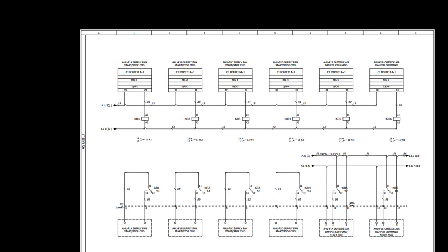Here are the terminal numbers of our panel: 9, 10 and 11. On terminal number 10 we have the on off command. This on off command is also 24 volt, but it is through the relay contact. When the relay opens, our damper will start opening, and when this relay is closed, our damper will start closing. But you can set this on the damper actuator. There is a direction switch, so by using that you can select it. So this is the concept behind wiring for the damper.